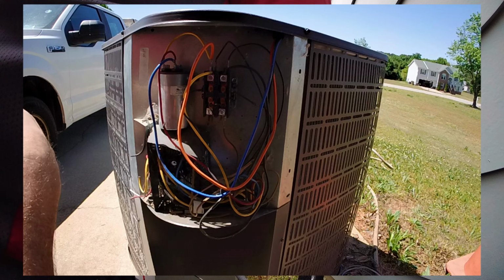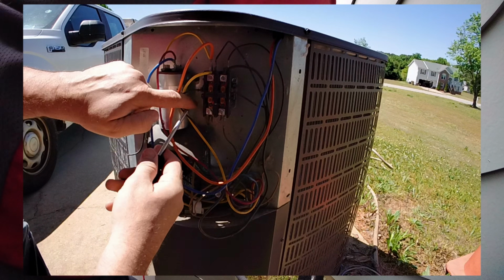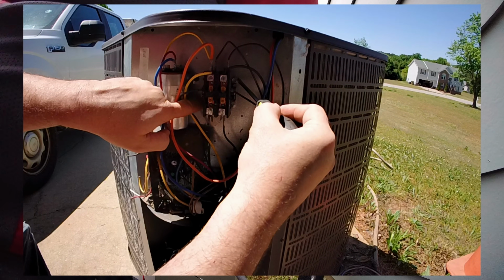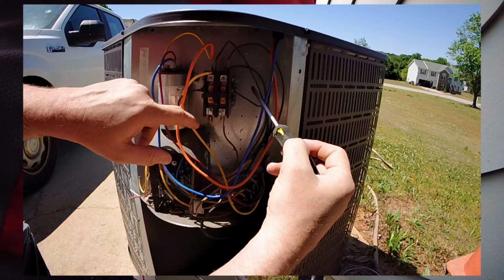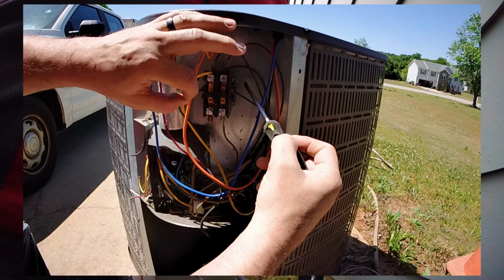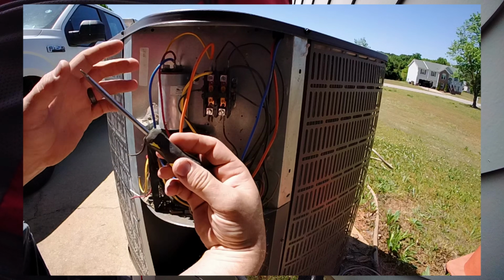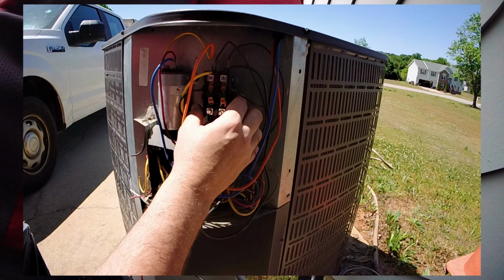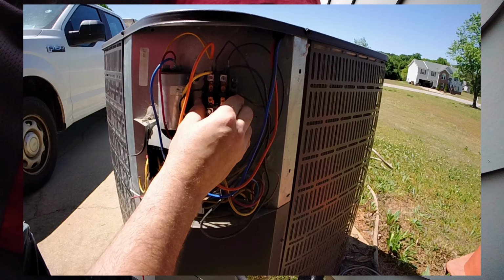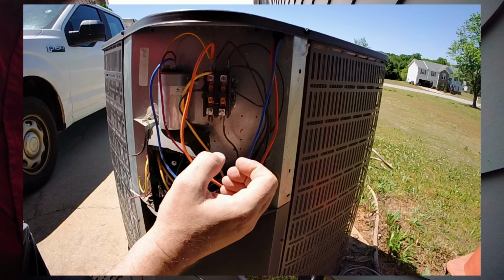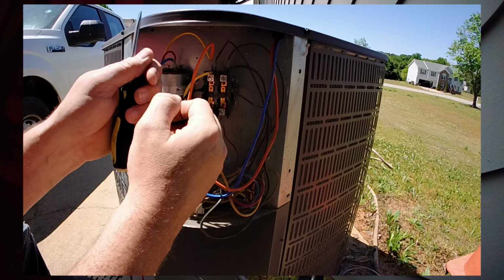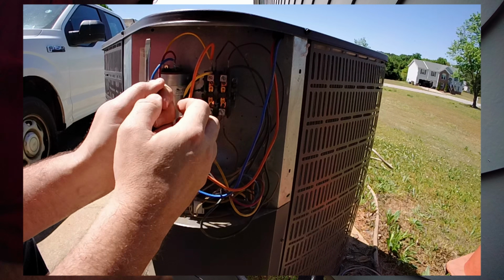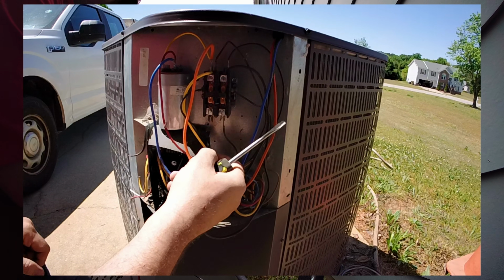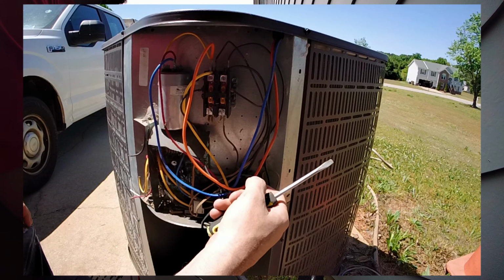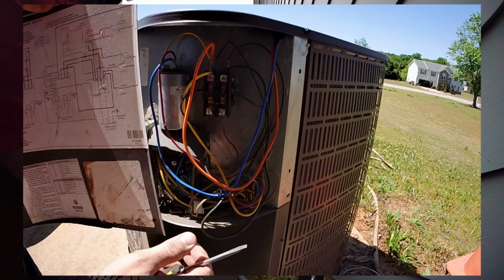As far as replacing them, it's easy enough. Typically, mounting wise, you'll have a couple of screws on either side, or sometimes there might be a nice little sleeve for them to slide into in the back. Either way, the way I like to do it is I just unmount the current contactor, pull it back a little bit, mount the new contactor, and that way I can just one for one take wires off, put them back. You don't really have to think about it much that way. You don't have to do it that way.